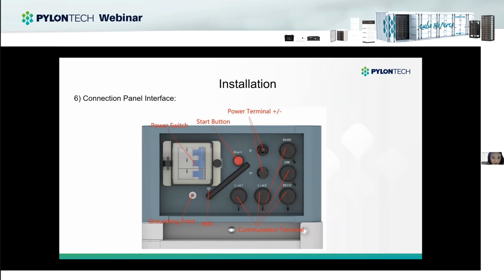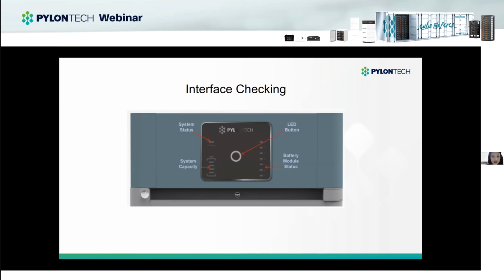The next 5 are communication terminals. Link 1 and Link 0 could realize the parallel connection of each BMS. The RS485 and CAN could connect the BMS to the inverter. And RS232 is to connect the BMS to the upper controller to do the monitoring and upgrade some advanced operations. This is the front side of the BMS. It shows the SOC, the status, and the number of batteries. And you could quickly find the faulty battery from it.